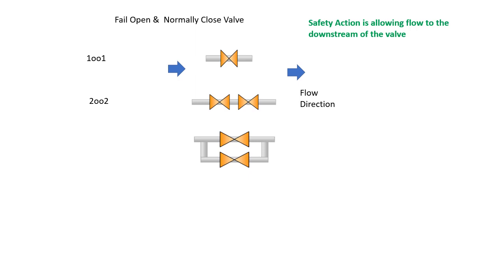And this is another combination, and this is 1 out of 2 combination, because if any of these two valves opens, right, due to the failure action, the water will go to the fire, and that will perform the safety action, right?